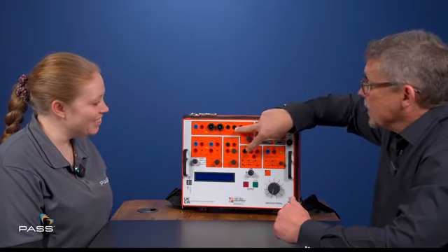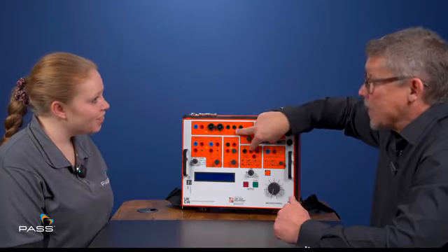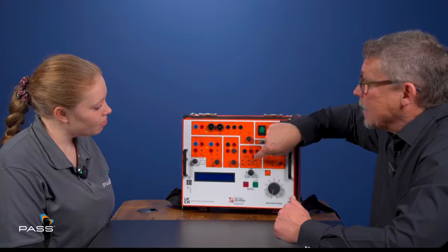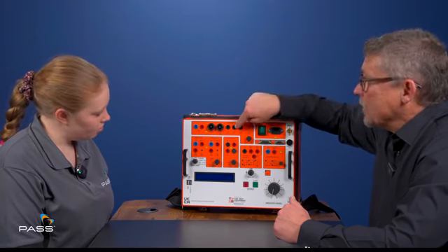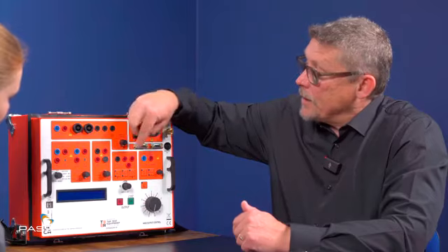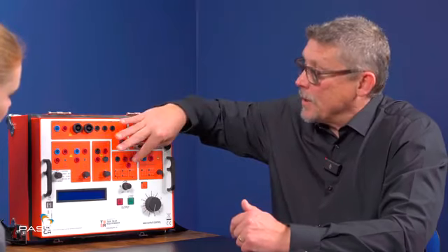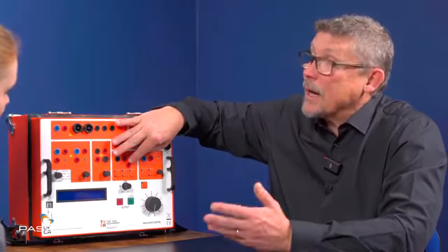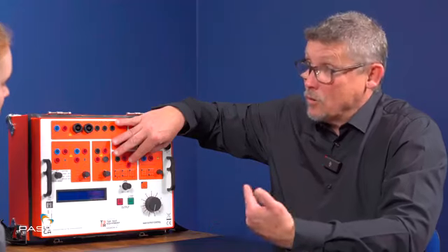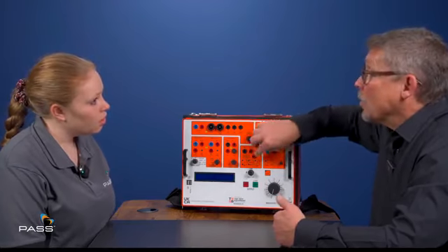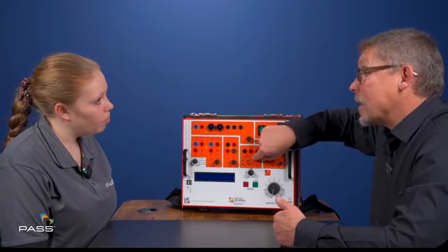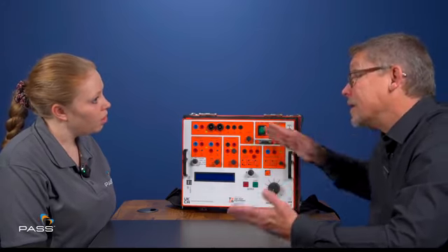One of them is I've doubled these channels up in parallel, putting a funny frequency in there with the 50 hertz in there. If I set that at 10 amp and I start that at 0 and bring it up, if I've got a harmonic relay that, say, trips at 20% of harmonic, I can make that up to 2 amps. And when I hit 2 amps, I will see that operate those harmonic relays. So these are some of the things that have set this unit quite apart from the others.